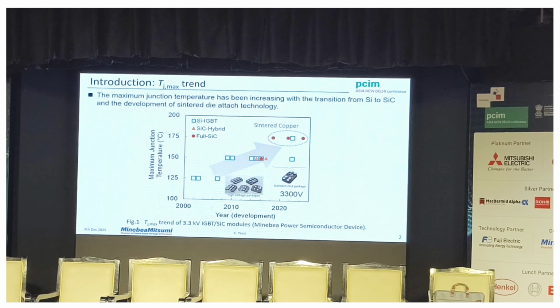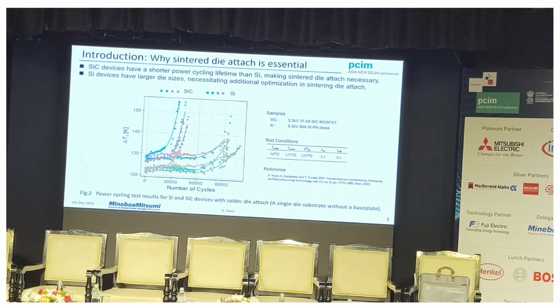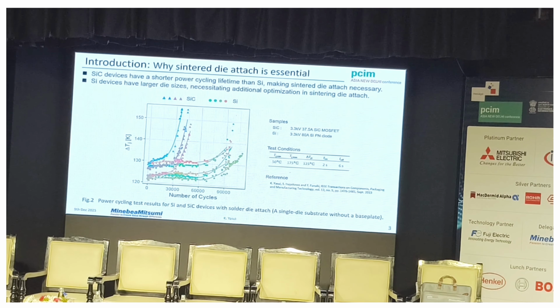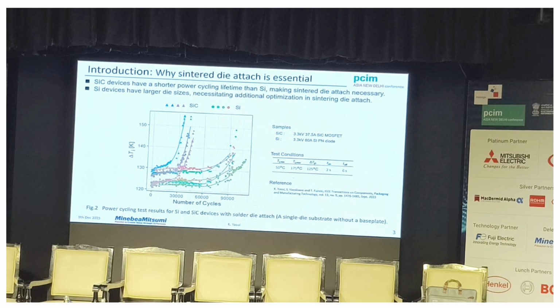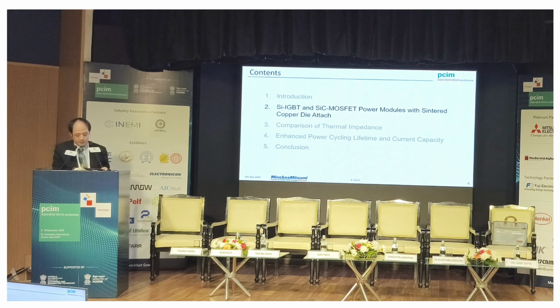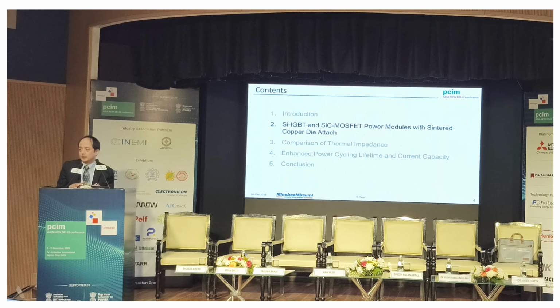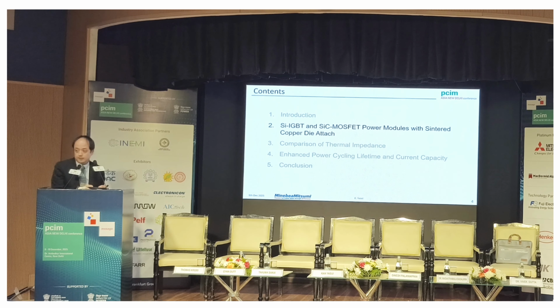Power cycle comparison was conducted for both silicon and silicon carbide devices. These are simple experiments for a single die substrate using conventional lead-rich solder. The horizontal axis shows the number of cycles, and the vertical axis shows the temperature swing delta Tj. The lifetime of the silicon carbide device, plotted as a triangle, was approximately half or one-third that of the silicon devices. Therefore, silicon carbide devices require more robust die attach technology, such as sintered die attach.